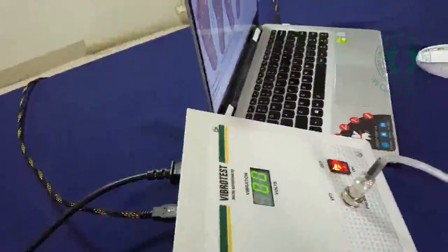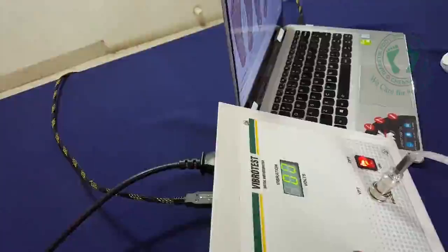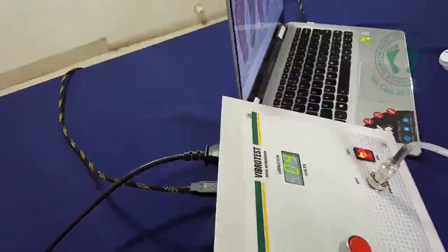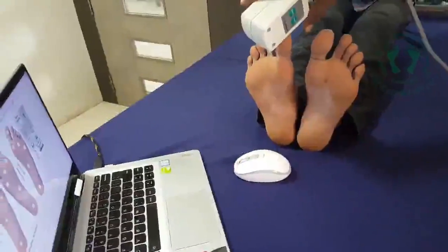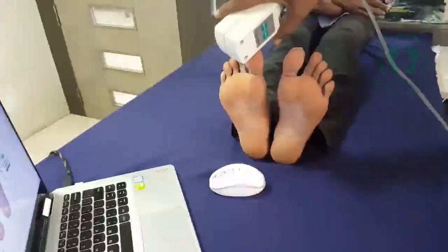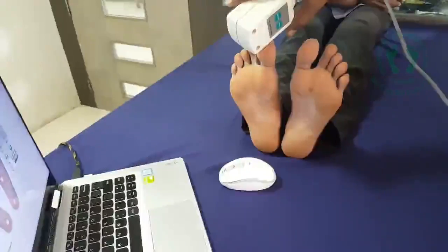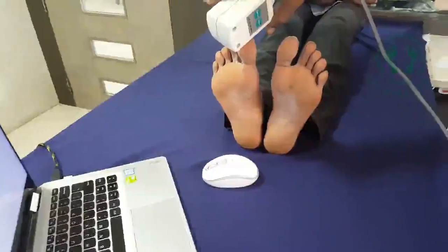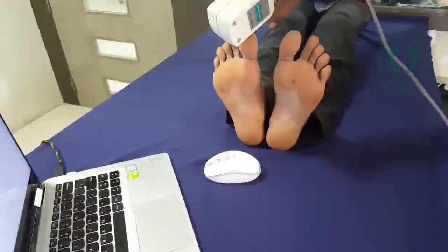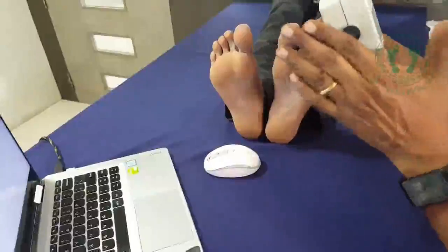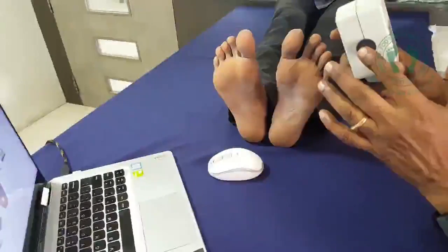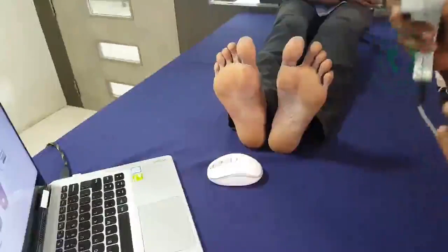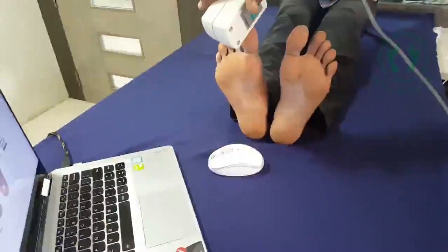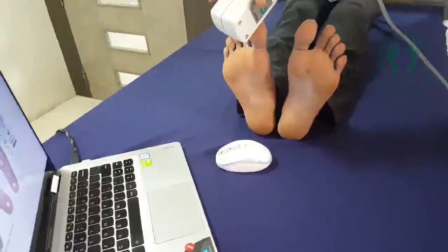So I will make it 0 and then I will test it. When I am testing it, we should not press the probe hard actually. It should be touched gently. When you are pressing hard, because of large force, the value can be attenuated, so you may get a wrong value, or sometimes because of continuous force on the tip, it might damage the parts inside. So always touch gently. So I am touching it, I am slowly increasing it.